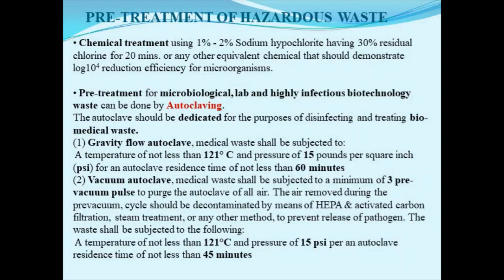And in the facilities, we're also using vacuum autoclaves or the horizontal autoclaves, usually used in the CSSDs, central sterile supply departments of the hospitals. The medical waste shall be subjected to a minimum of 3 pre-vacuum pulses to purge the autoclave of all air. The air removed during the pre-vacuum cycle should be decontaminated by means of HEPA and activated carbon filtration, steam treatment, or any other method to prevent release of the pathogens. The waste shall be subjected to a temperature of not less than 121 degrees Celsius and a pressure of 15 psi for an autoclave residence time of not less than 45 minutes. So for vacuum autoclaves, the holding time is 45 minutes, but for gravity flow autoclaves, which we are using in most of our facilities, the holding time should be 60 minutes.